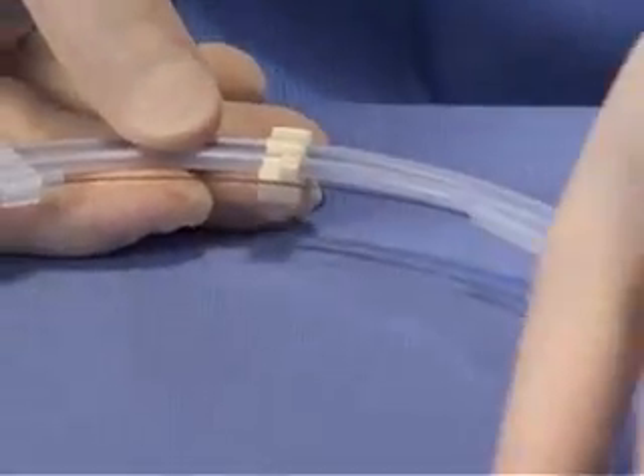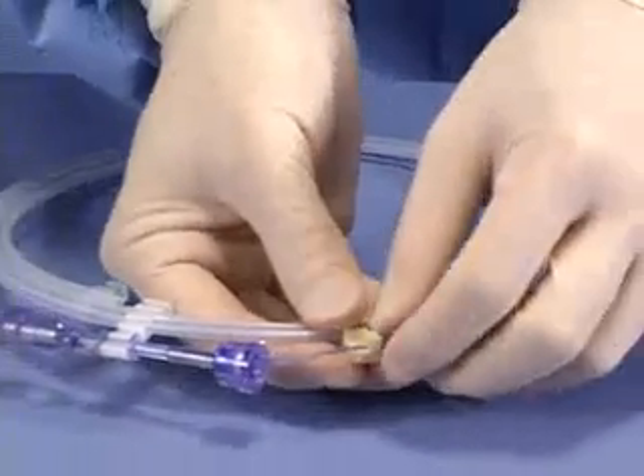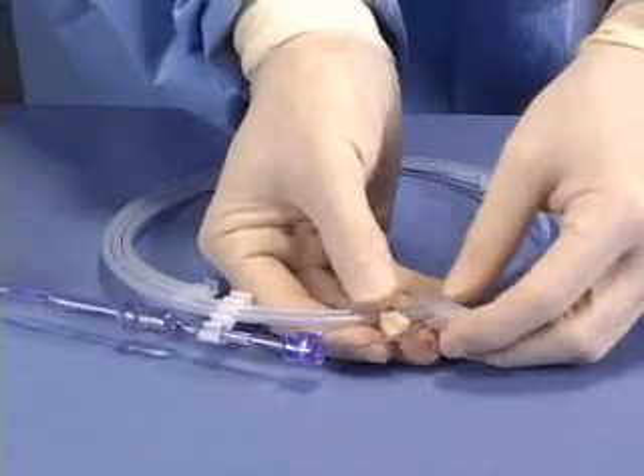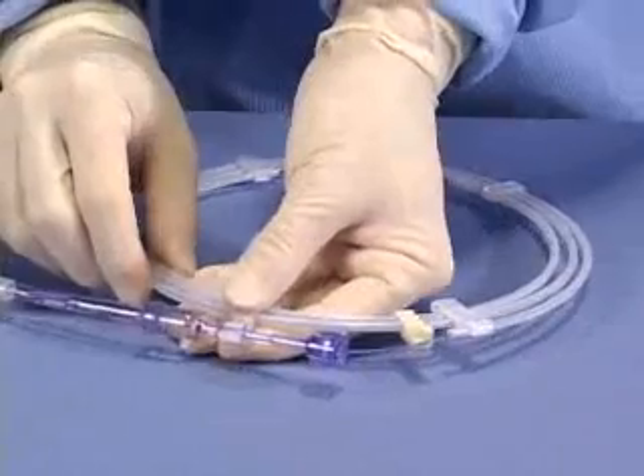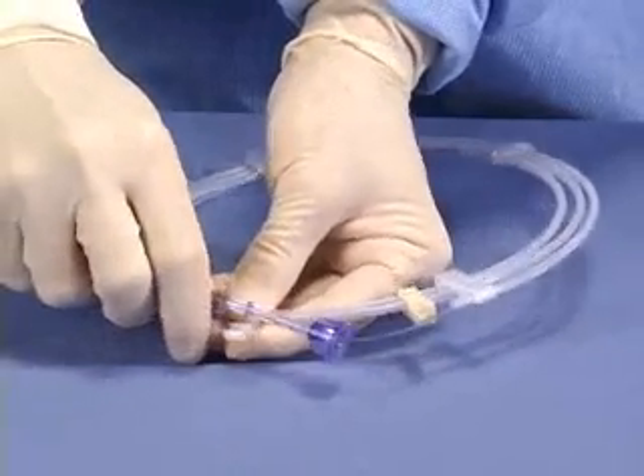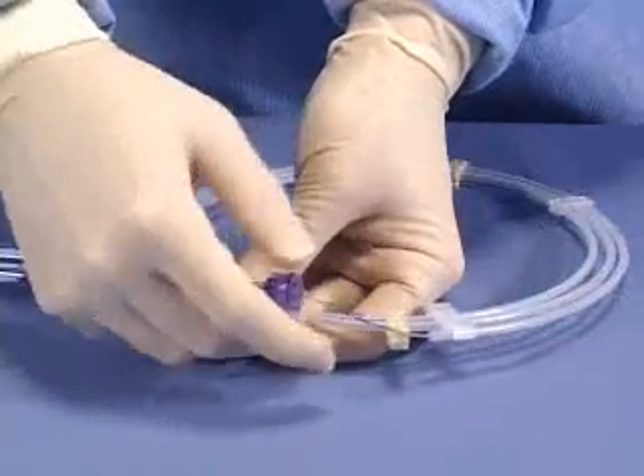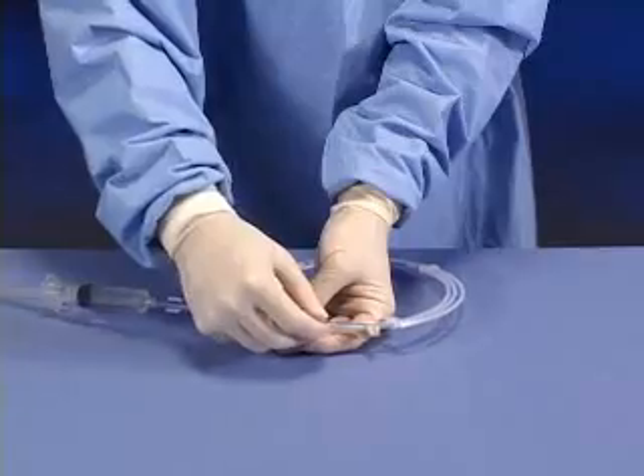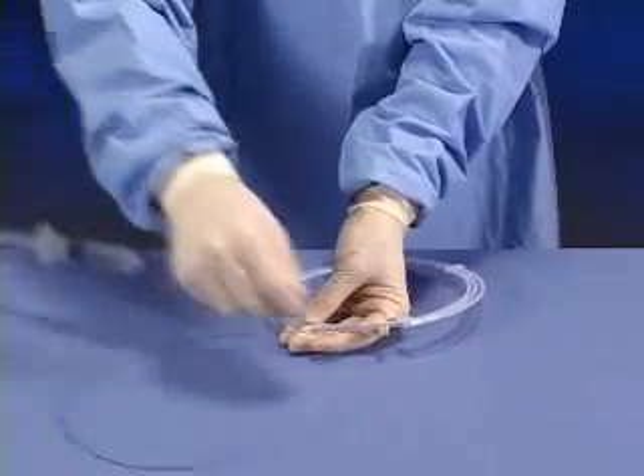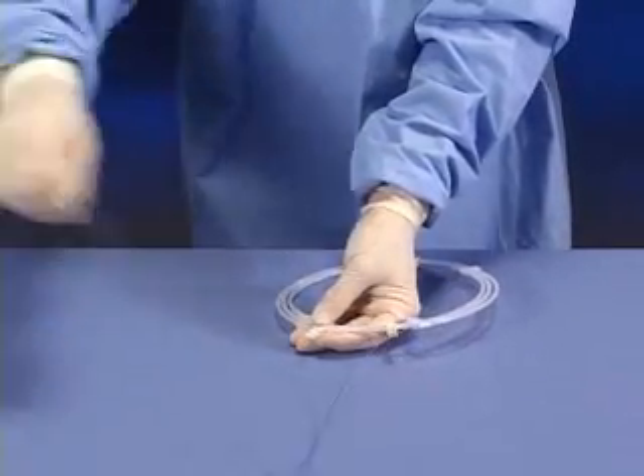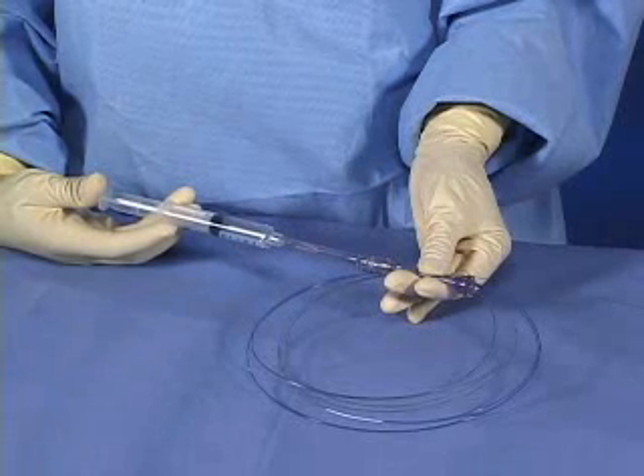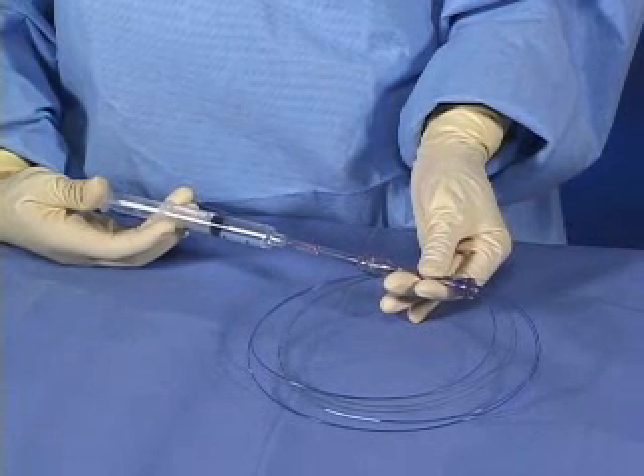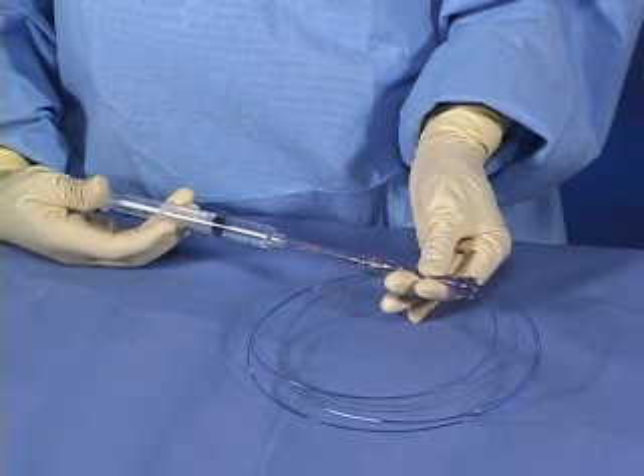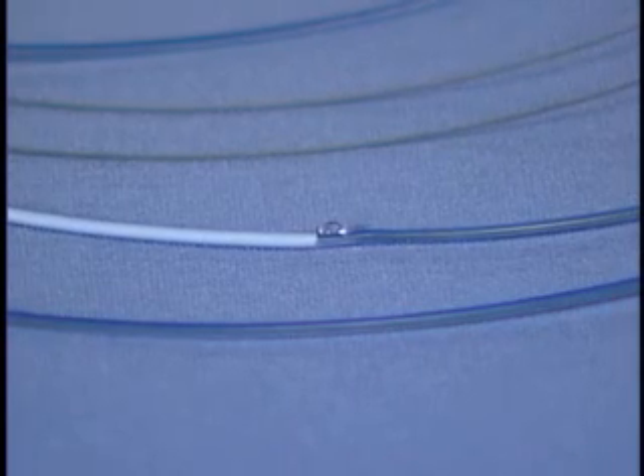Release the device from the attachment hooks on the dispensing hoop and remove it from the hoop by pulling on the flush tool. Make sure that when removing the device from the packaging hoop that you grip the delivery sheath to ensure that it is held within the flush tool. Flush again to remove all air from the sheath. Observe fluid exiting the proximal end of the delivery sheath.